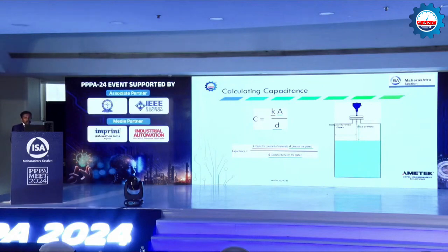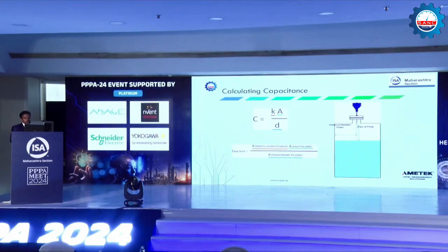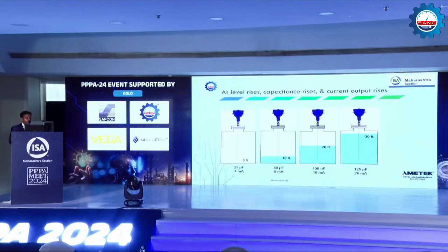Here in level measurement, A is the area of the plate we are measuring, and D is the distance between the two plates, which is the tank wall and the transmitter probe. So with this formula, we can calculate the capacitance. So how has this been implemented in level measurement?